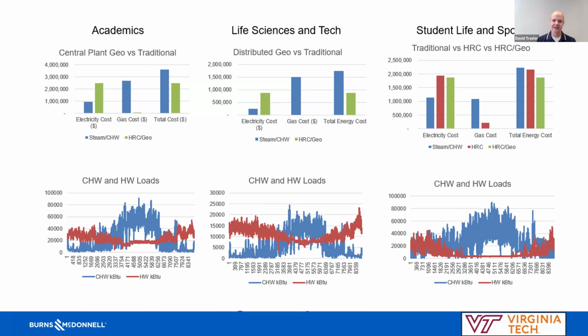When I first did this analysis, I got to the student life and sports district, and I was curious why there aren't the same amount of savings in this area. And it helped me when I looked at them all side by side. So on the bottom of each one of these is an hourly heating and cooling graph for the different areas. In the life sciences district, there's a pretty high hot water load even in the summer. And a lot of that's because these buildings have a lot of dehumidification in them. And there are a lot of larger campus buildings. So even if they're not occupied, you usually keep them climate controlled.